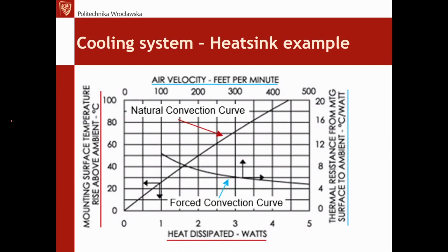In the case of the heatsink, airflow is very important and plays a very important role. Here is an example comparing natural convection and forced convection. With natural convection, when there is 1 watt to be dissipated, the temperature rise is about 25 degrees. With 2 watts, the temperature rises about 50 degrees above the ambient temperature of the junction or case of the device, and so on - it rises linearly with the dissipated power.